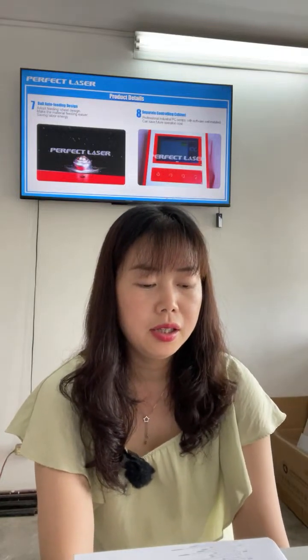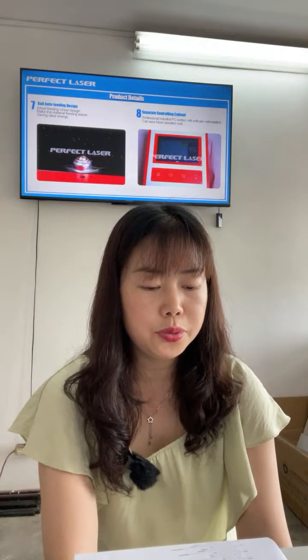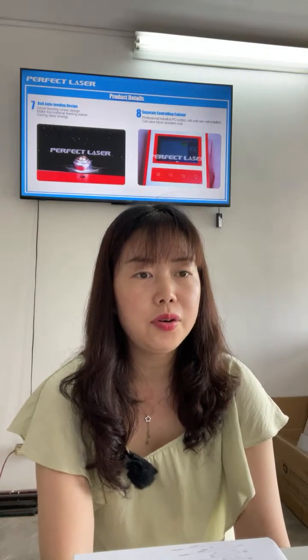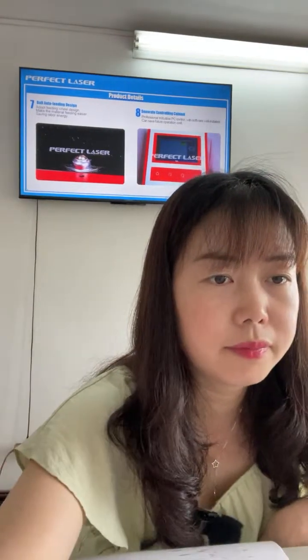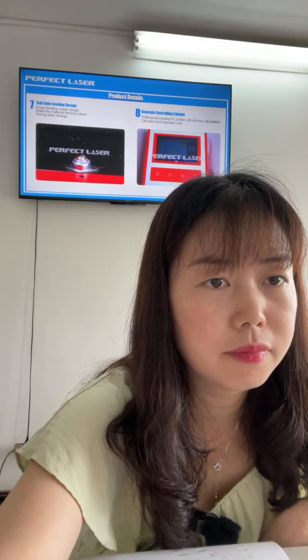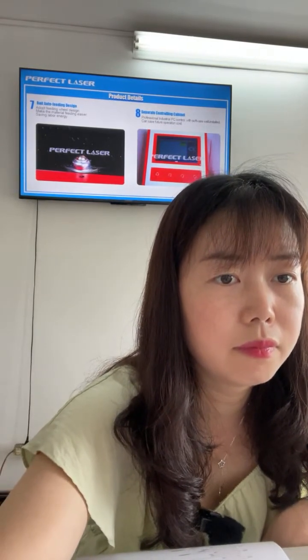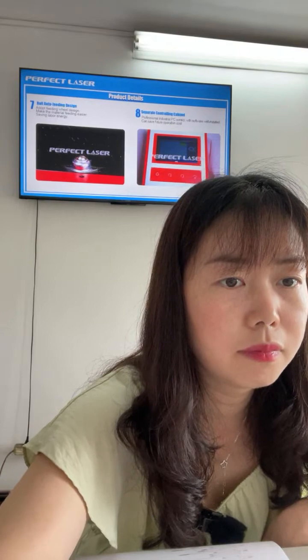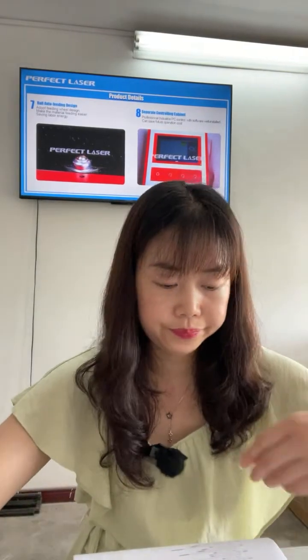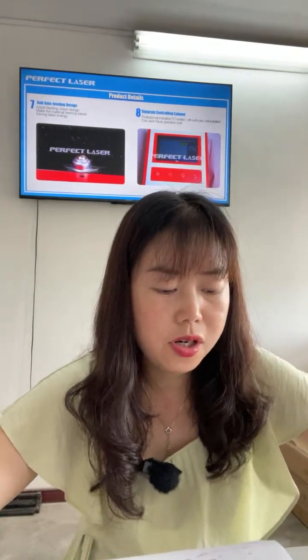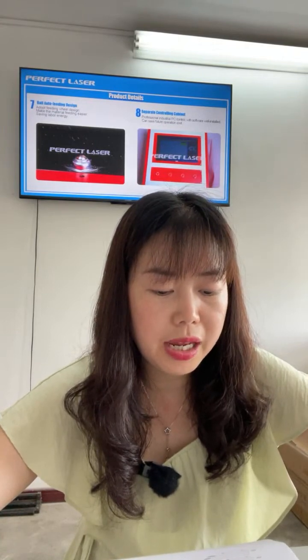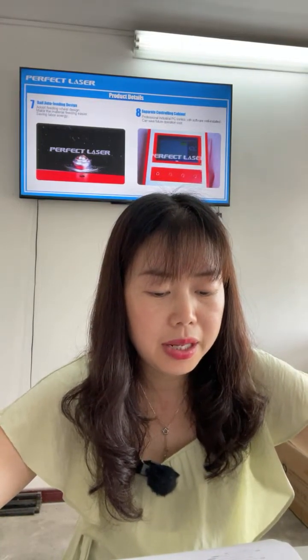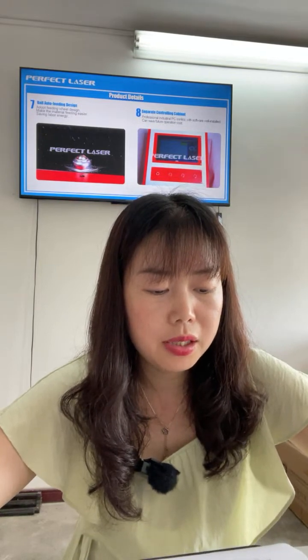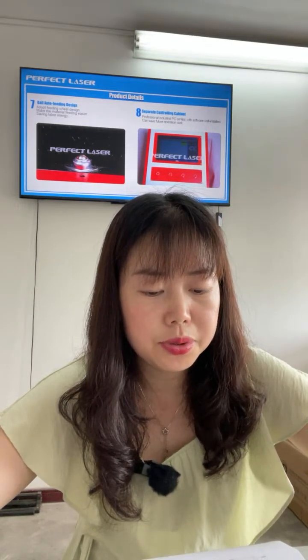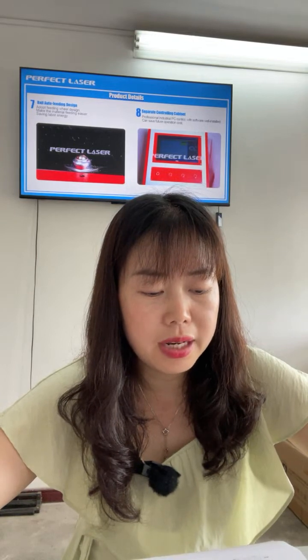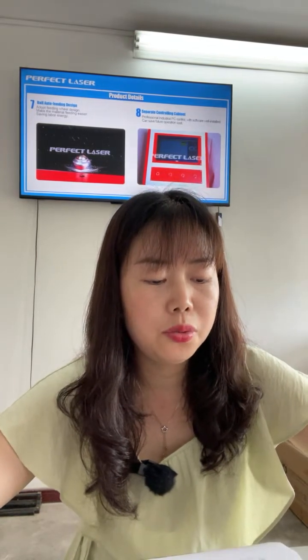About maintenance. First, the machine needs to work in a clean environment. The focus lens needs to be changed every half year. Number 3, the water in the water chiller needs to be changed every month if you work every day. Number 4 is the lubrication.